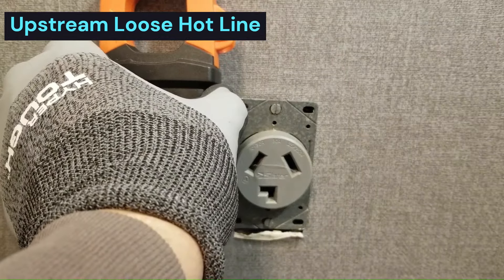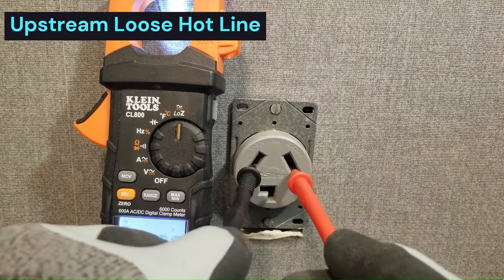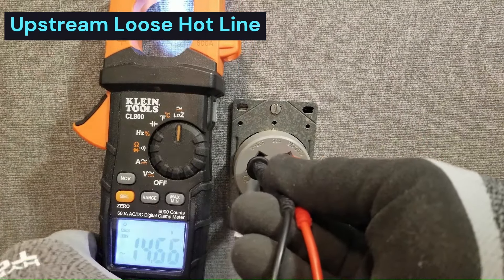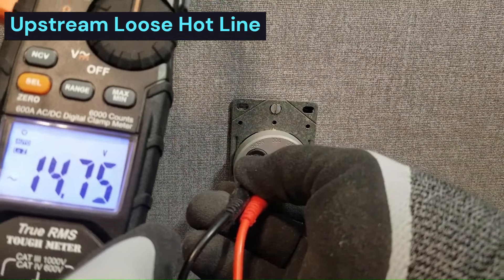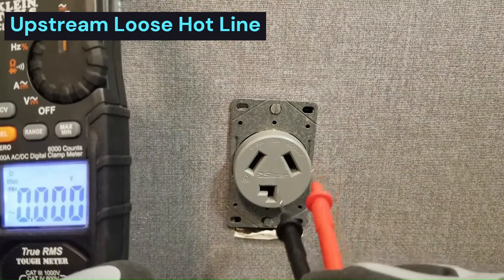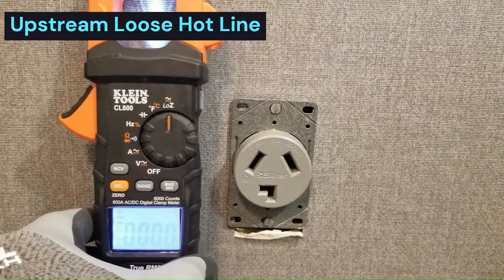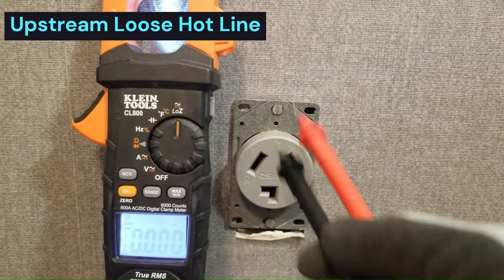This is the Klein CL800 low-Z meter - there's a link to this in the description of this video. Let's check from here to here. Now using the low-Z meter, we have 14.75 volts. So that 3,000-ohm load is actually dragging that voltage all the way down. But the low-Z meter can also tell you which one of these legs is bad.